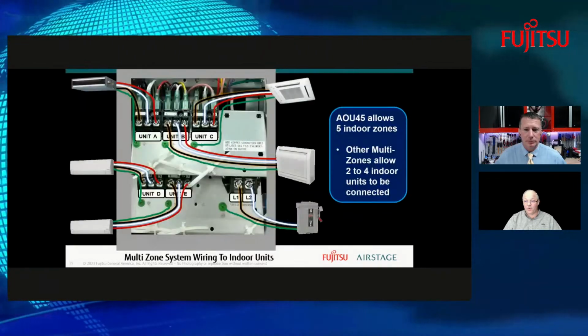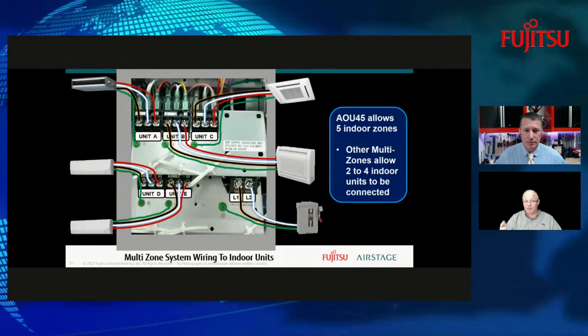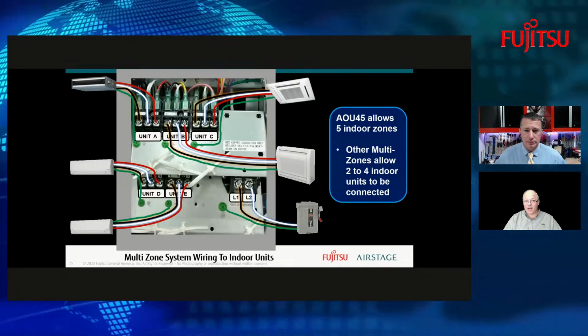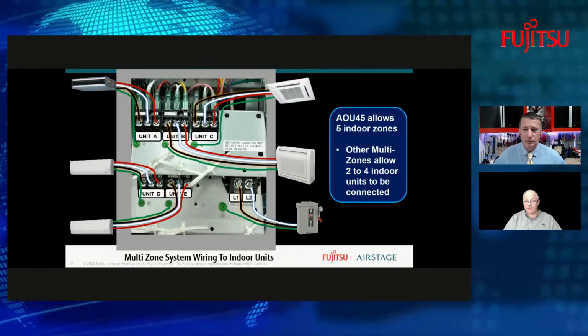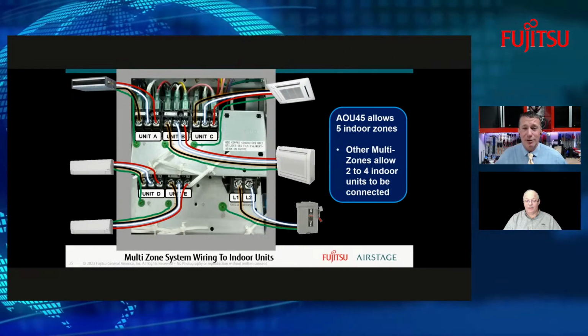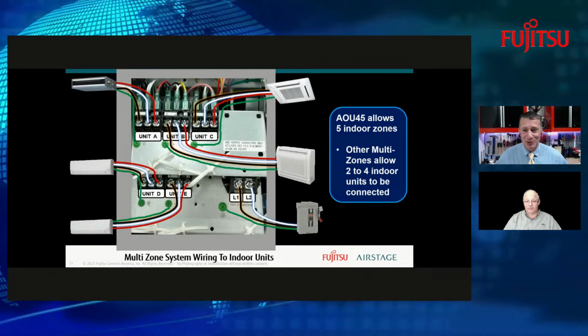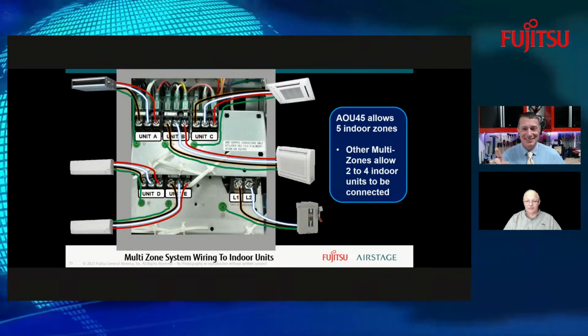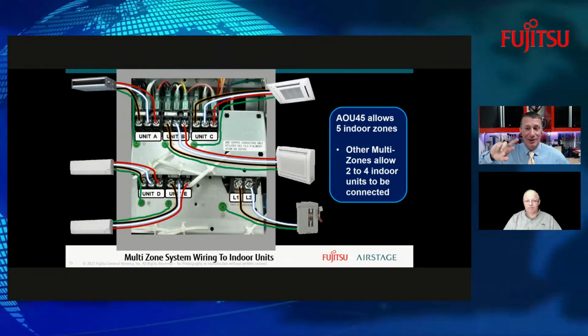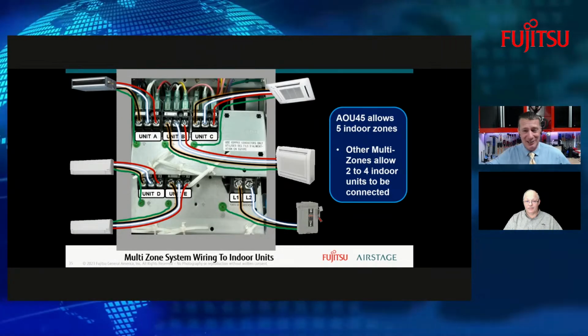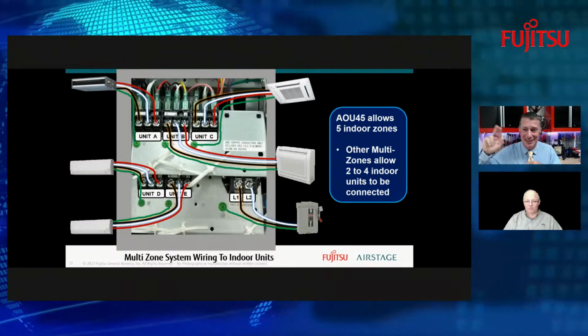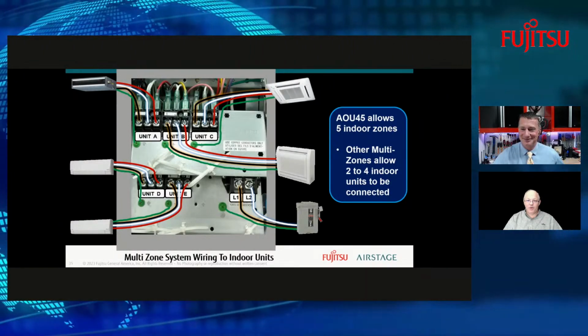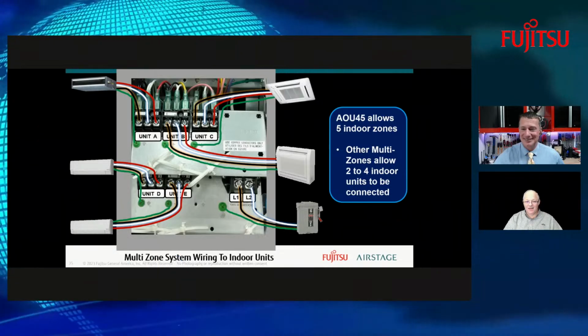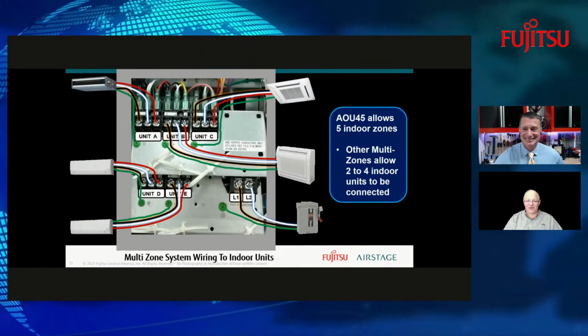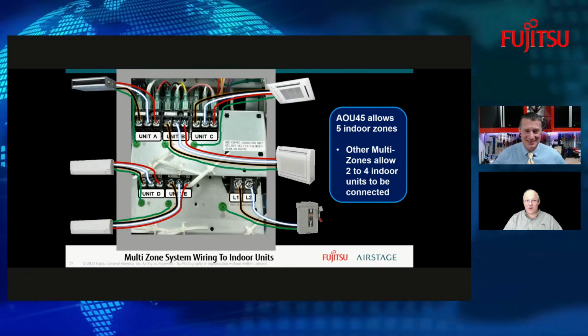So if you did take this 45 model of ours, this is how it would look if you connected up different styles of indoor units to the outdoor unit with the power wires. And very important to make sure that our refrigerant line sets are matched to the control wires for each particular circuit. Seen it way too many times out in the field where we get our lines crossed, and so we may be trying to operate a unit and sending refrigerant to another one that has had no signal to actually turn on. Yeah, there's nothing like having refrigerant flowing to an indoor unit that the fan's not even calling. Nothing's calling. It's just getting refrigerant. Yeah, exactly. That can happen if you don't do your install and label where you're running your line sets to.